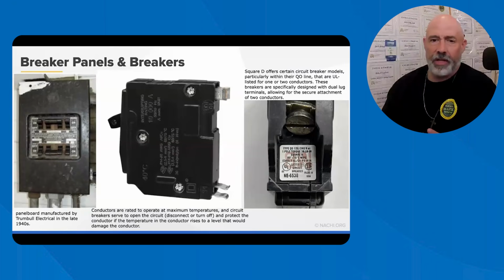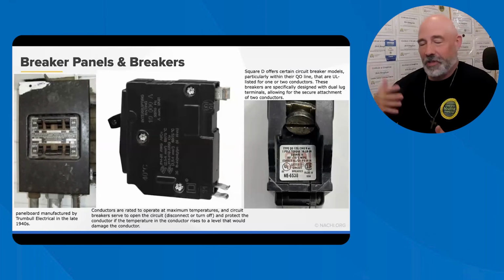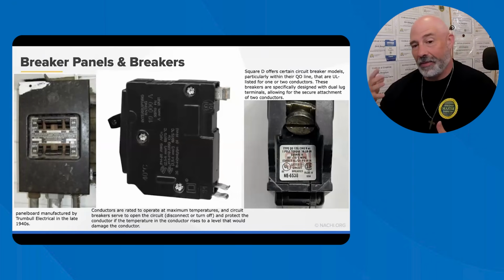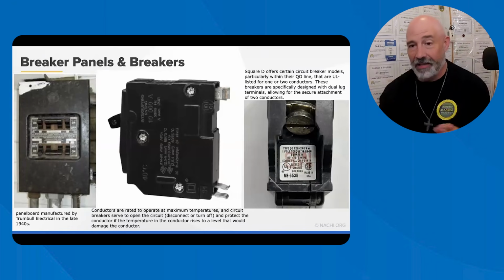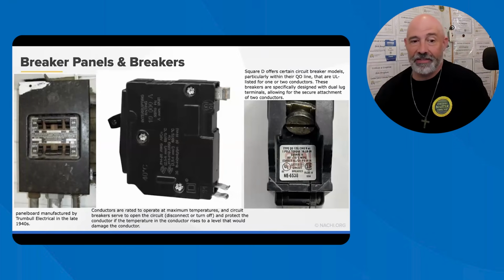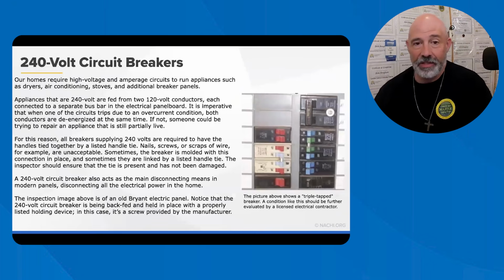Circuit breakers actually fall into four different categories. Number one is the 240 volt double breaker. You got the 120 volt single breaker, and you got the GFCIs, and then you got your AFCIs. All of these require some specialized knowledge so that you understand what's going on. Remember, we are talking about energized components. Safety is the primary focus. This is paramount in investigating any electrical devices.